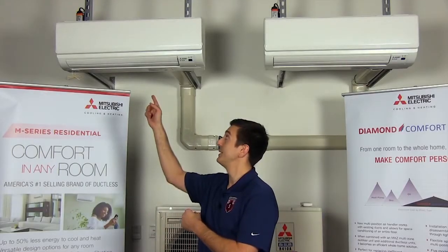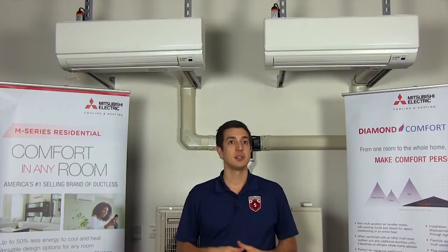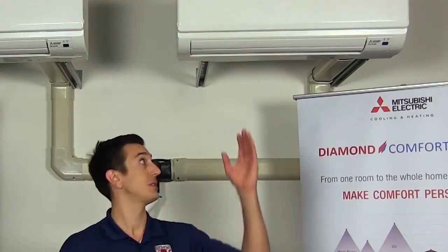Our last example is something that we run into quite often. The situation is when multiple systems are installed on the same job site in the same vicinity, almost side by side, such as system one and system two. What would happen if the wires between those systems were crossed? So system one actually went into system two, and system two went to system one. That can cause the PA error code. Let's take a look and see how it happens.